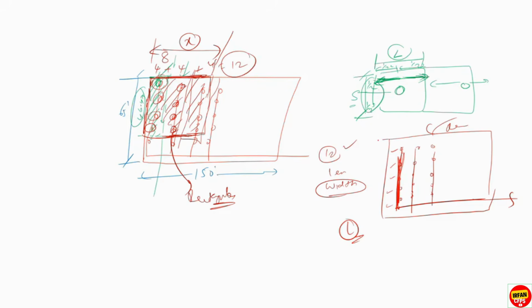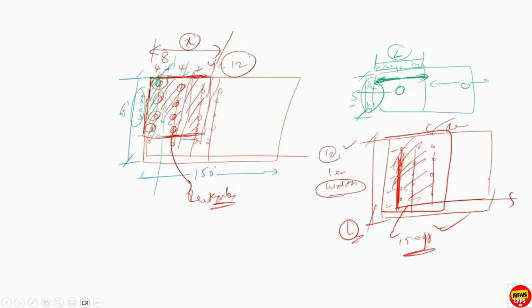They don't calculate the length. They just calculate the total length of the room or the floor, or the number of sprinklers in the branch lines, and just calculate 1500 square feet from here, and proceed with the calculation. You cannot do it this way.